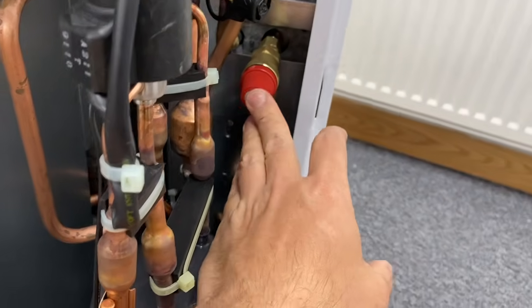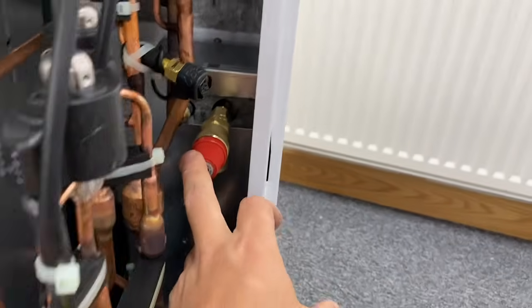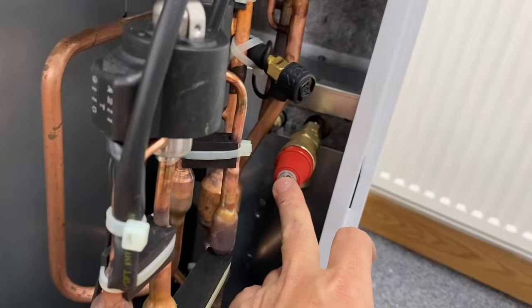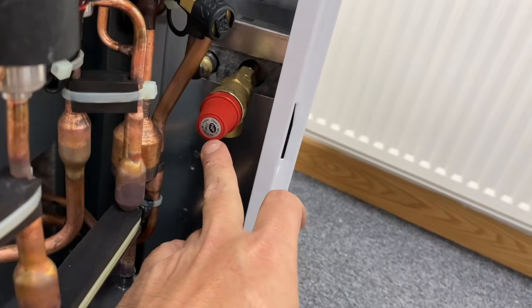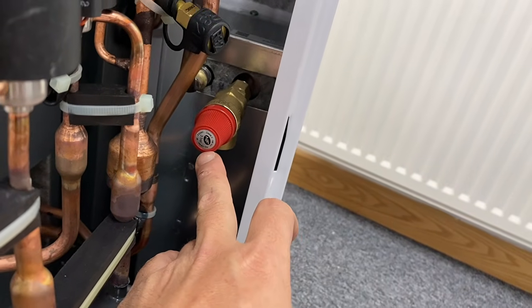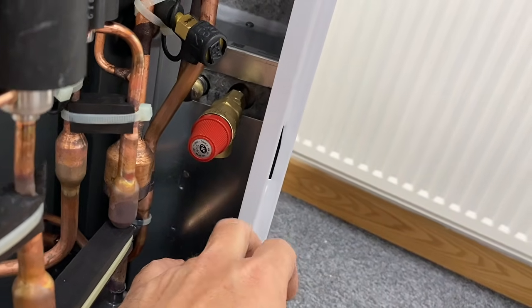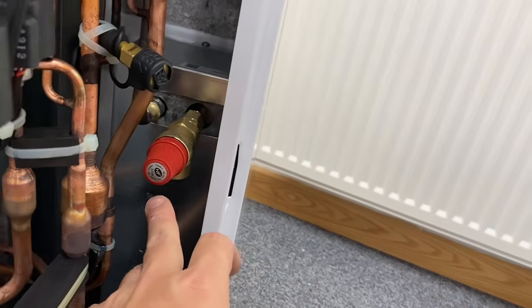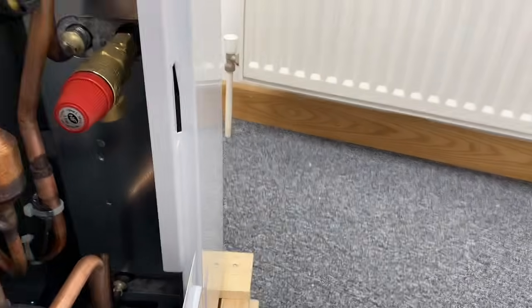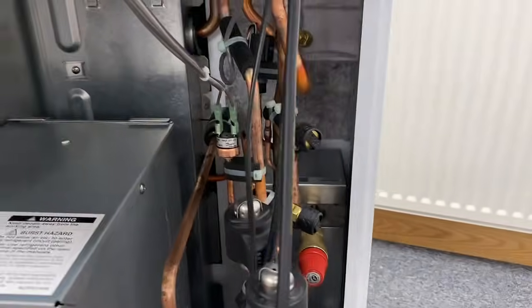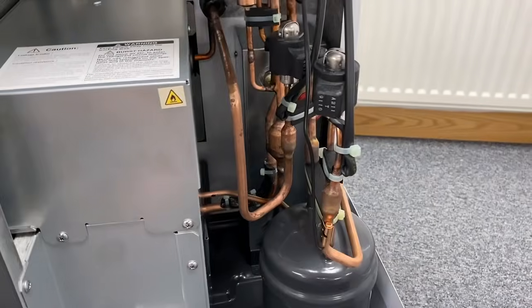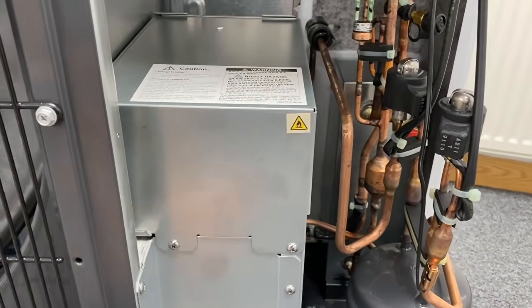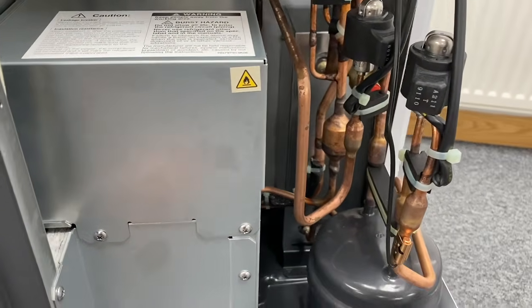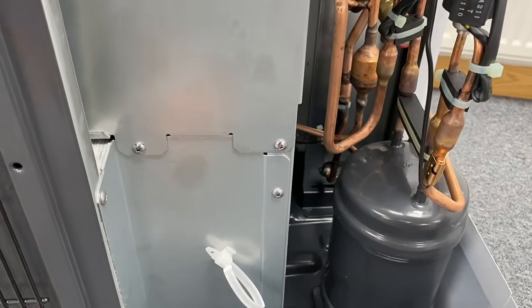Also, you'll find on the R32s, this is new on the heat pumps. This is a pressure relief valve for the refrigerant. So if anything ever over-pressurizes the refrigerant, that needs to be connected to make sure that it will allow a disperse should anything happen out of the ordinary. It's very, very rare, but again, it's another safety mechanism to consider.